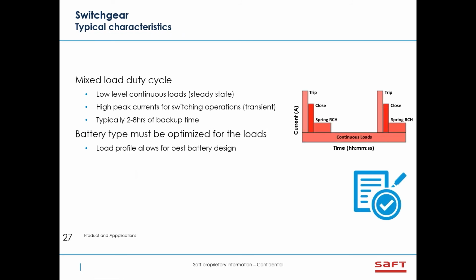This is just a typical duty cycle for a switchgear. Typically, you have the trips and closes and then the continuous loads. And depending on your application, you tell us this profile, and then we can optimize the battery for that particular load and size the battery to your profile.